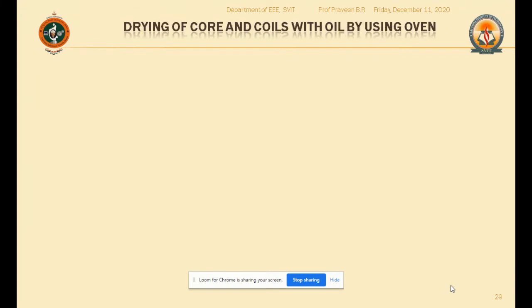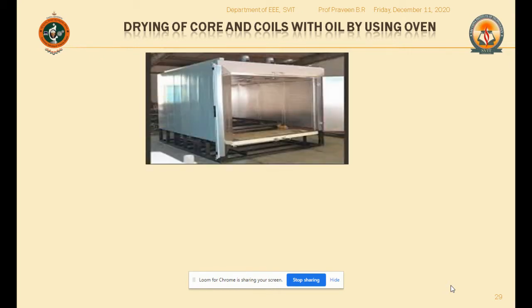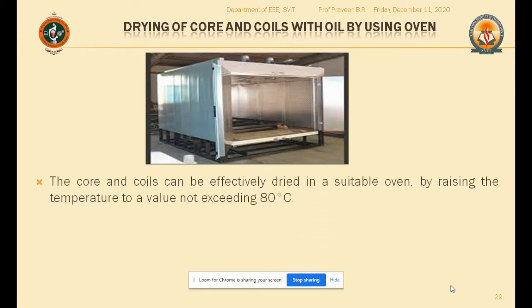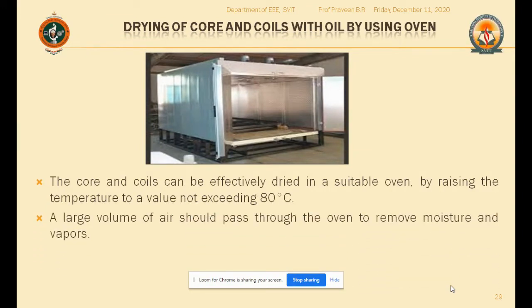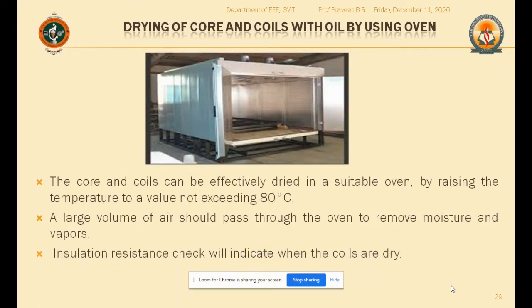So let us move to the first method, that is drying of core and coils with oil by using an oven. This is called the oven, where you are going to heat the transformer windings. The heating should not exceed 80 degrees centigrade. The cores and coils which are dried are kept in a suitable oven, and the temperature is raised up to 80 degrees centigrade. A large volume of air should be passed through this oven, which removes a lot of moisture and vapor content.